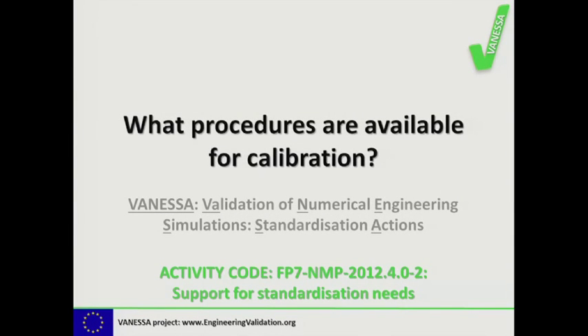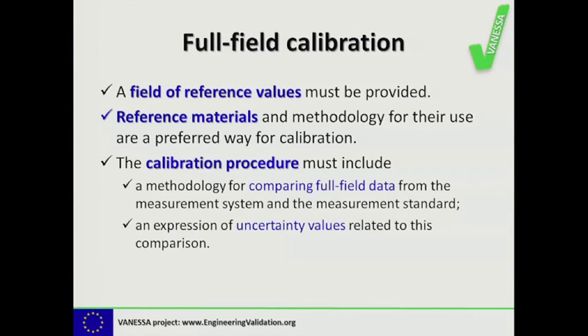What procedures are available for calibration? Since we are talking about full-field measurements, we need full-field calibration to be addressed. For full-field calibration, the first thing you need is a field of reference values rather than a single one. Reference materials and the methodology for their use are a preferred way for calibration. The calibration procedure must include a methodology for comparing full-field data from the measurement system with the measurement standard or reference material, and it needs an expression for uncertainty values related to this comparison.